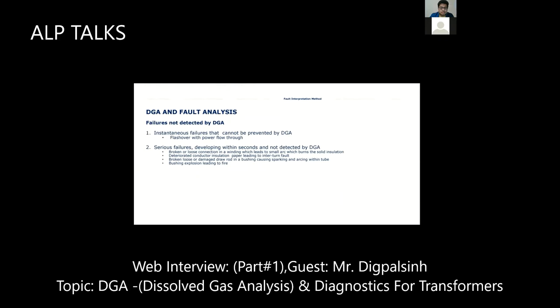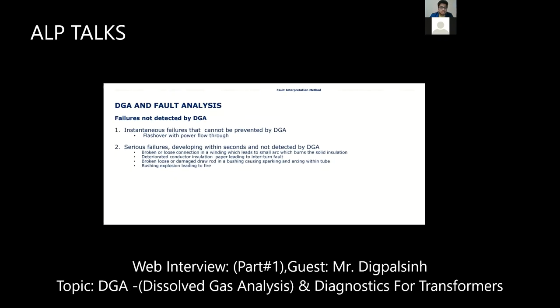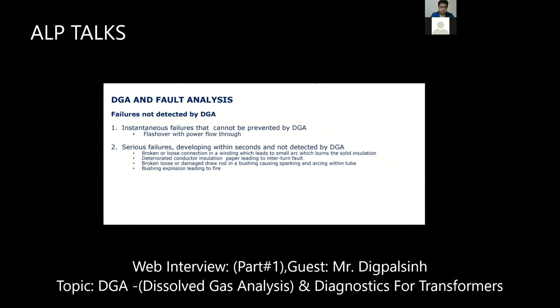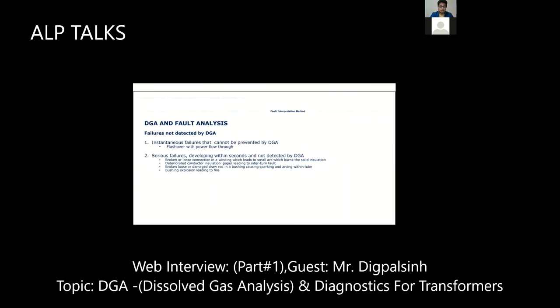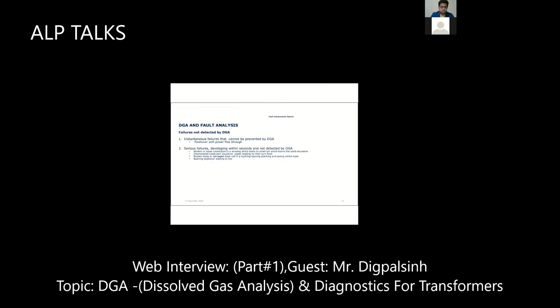There are failures which cannot be detected by DGA, like instantaneous failures that cannot be prevented. If your transformer is running healthy and there is a short circuit somewhere in your substation, some instant fault will occur. You cannot go back to three-month-old DGA data and analyze dissolved gas. Any instant flashover cannot be captured by DGA. Then second is a serious failure developing within seconds; you can again call it instantaneous failure, which is not detectable by DGA.